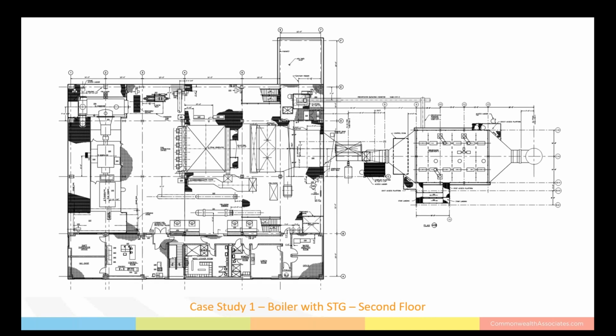This is the second floor of the same site. Typically above the electrical room is where we like to place the control room. This control room also includes an I&C shop and a shift supervisor's office. Above the maintenance shop and water treatment area are the bathrooms, lockers, break room, and a couple of offices. To the left is the steam turbine. The lower side has room for rotor pull, and the upper side, where the condenser is, has room for the condenser pull space. Just below the boiler, I want to point out 2 heat exchangers and the length of the pull space required for cleaning and maintenance that often gets overlooked.